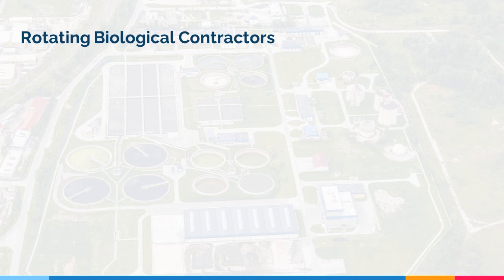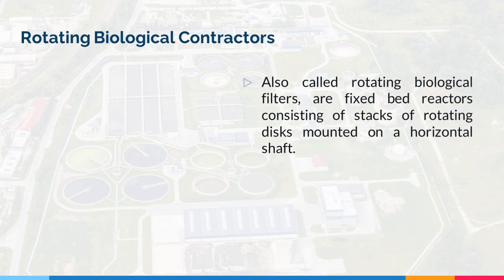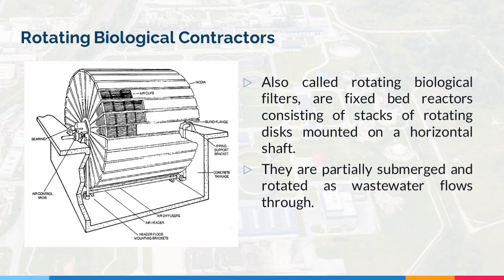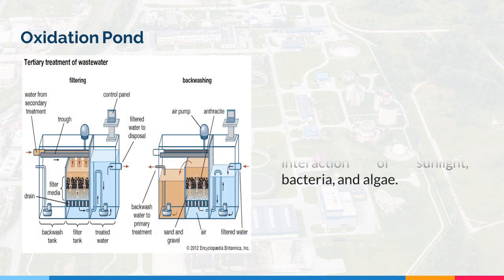We also have rotating biological contactors, also called rotating biological filters. These are fixed bed reactors consisting of stacks of rotating discs mounted on a horizontal shaft. They are partially submerged and rotated as wastewater flows through. Oxidation ponds, also called lagoons or stabilization ponds, are shallow ponds designed to treat wastewater through the interaction of sunlight, bacteria, and algae.